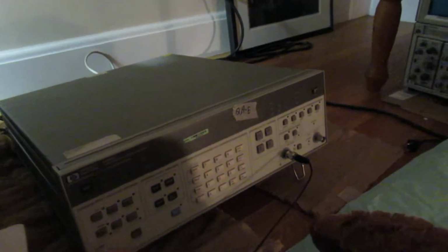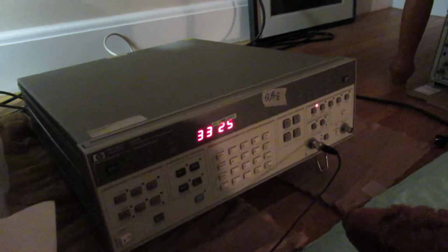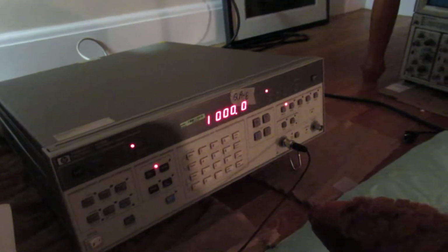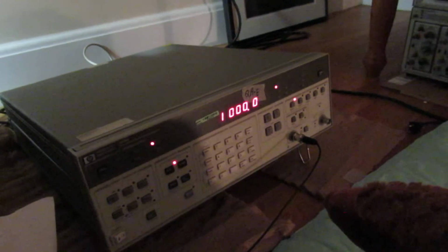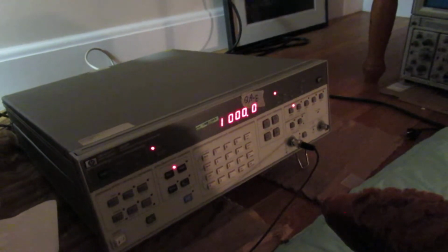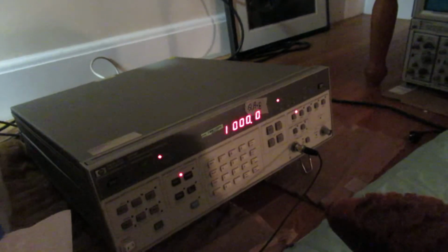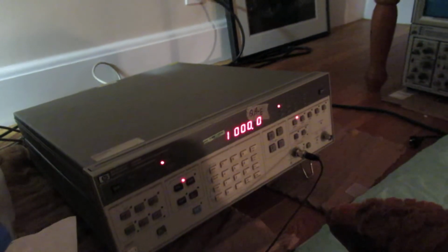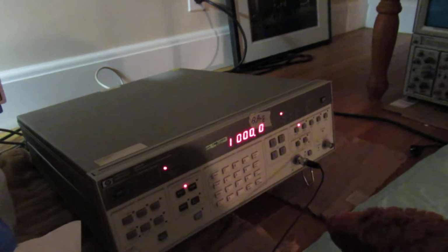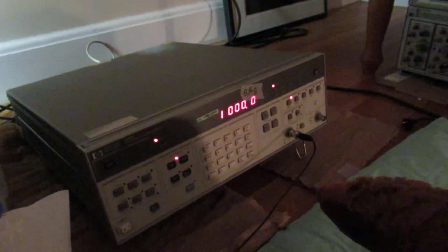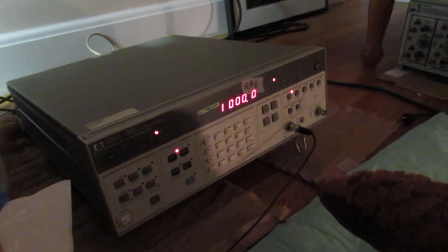Oh, there's one other thing I should replace in there, and that is the one error message I get with this guy. I'm just gonna turn everything off for a minute so you can appreciate the quiet. And fail 3.6. Yeah, the lithium battery that stores the saved settings, I suspect, and definitely the calibration data in there needs a change. But otherwise, it's a beautifully functional instrument.